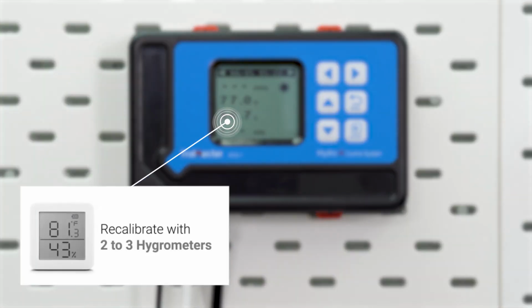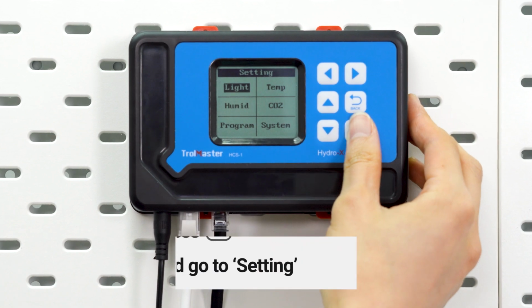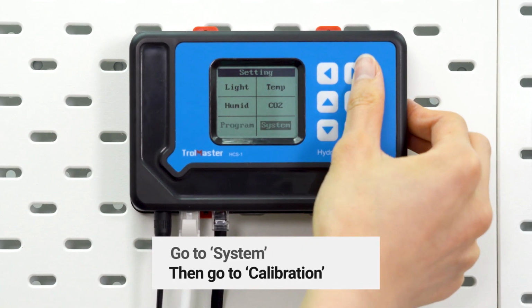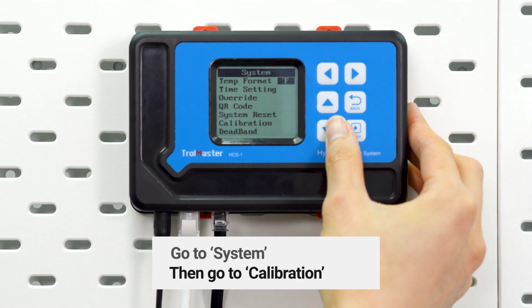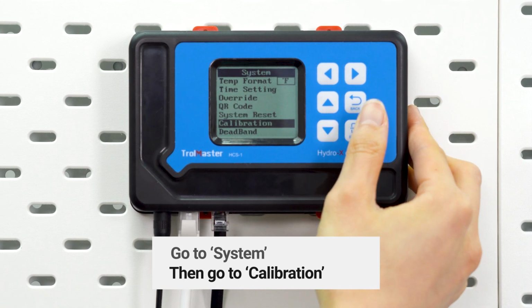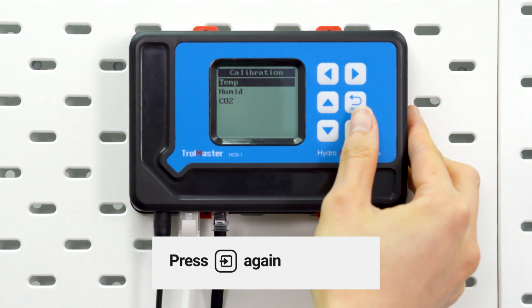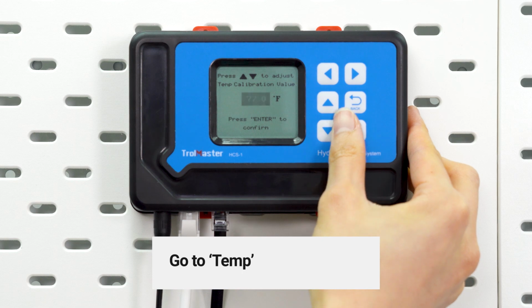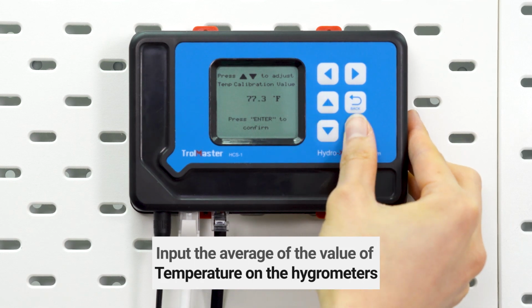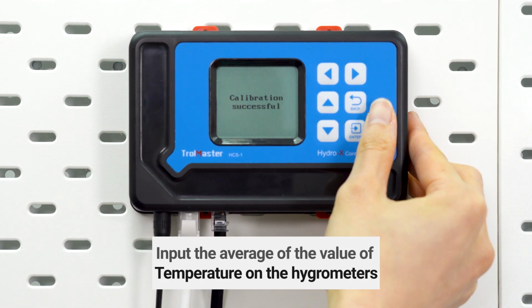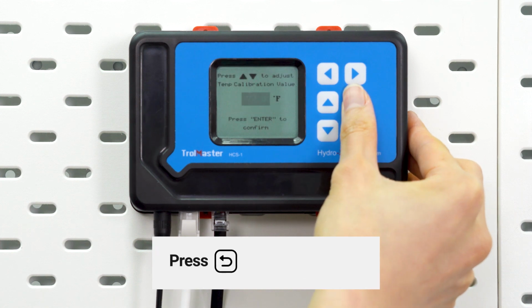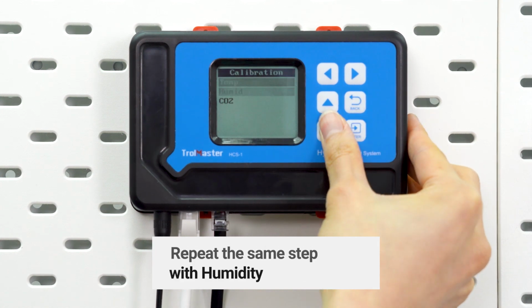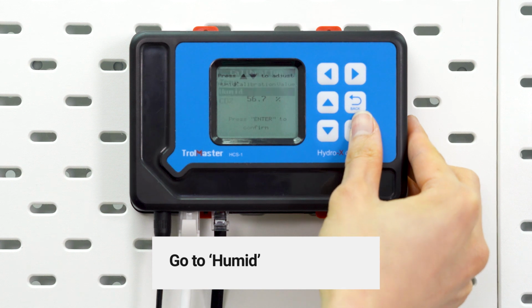Recalibrate it with 2 to 3 hygrometers. Then press the Enter button to go to the setting page and choose System. Then Calibration. And go to Temperature and input the average value of the temperature on the hygrometers. Repeat the same steps with humidity.